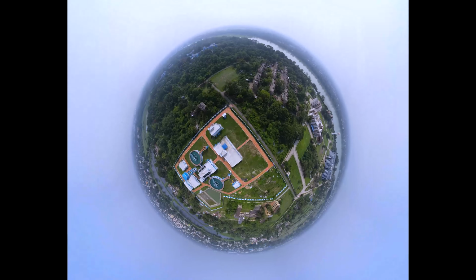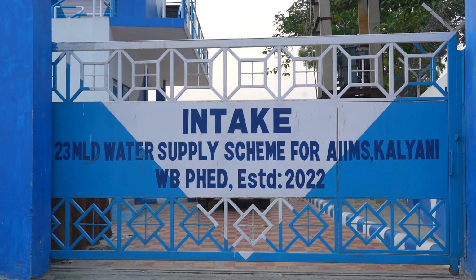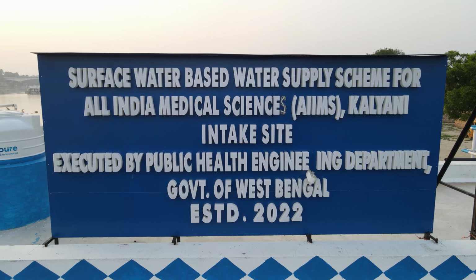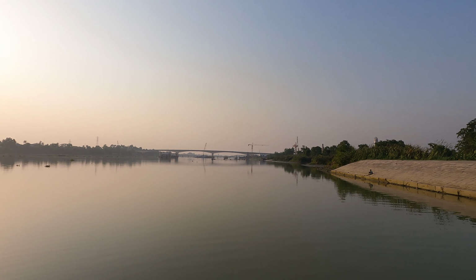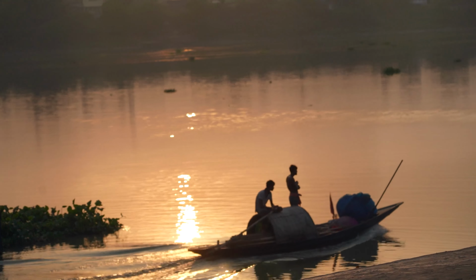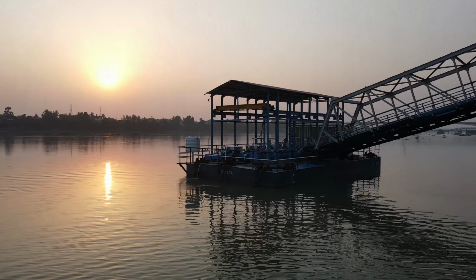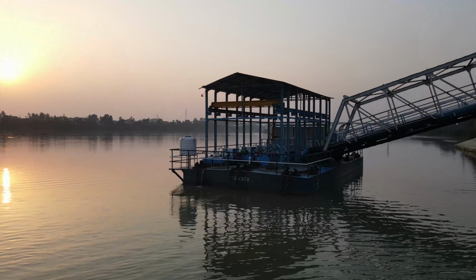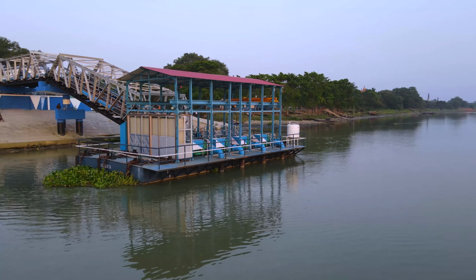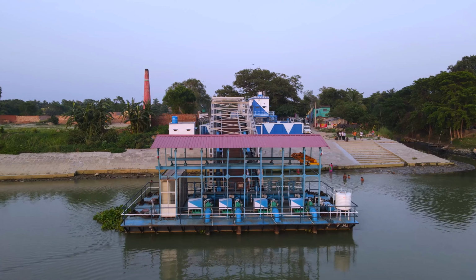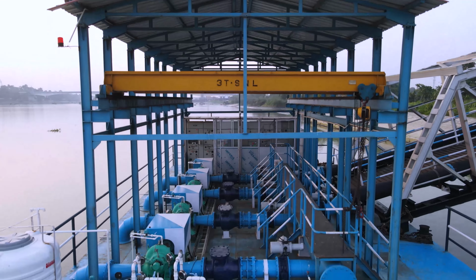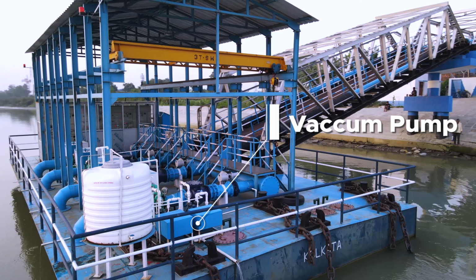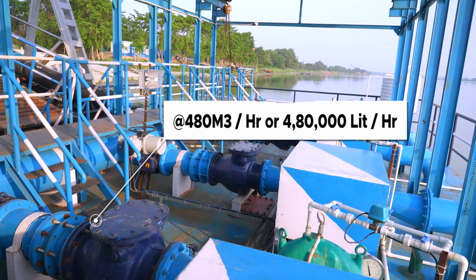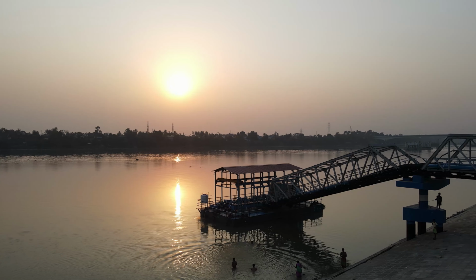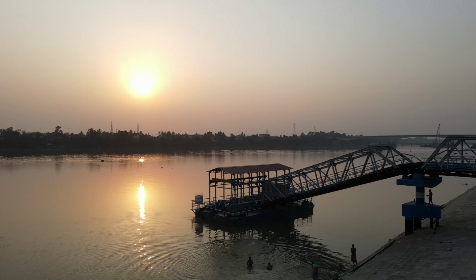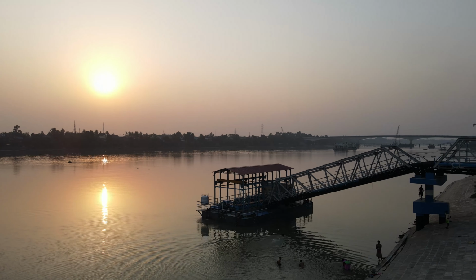For Kalyani AIIMS WTP project, the intake house is situated far away from the main plant at Chor Kachrapara, near Kalyani Ishwar Gupta Setu. Here, the pumps for lifting of the water from the river are set up on this floating jetty, specially built for this purpose. There are 2 vacuum pumps and 4 raw water lifting pumps, each having a capacity to deliver 480 meter cube per hour or 480,000 liters per hour of water.